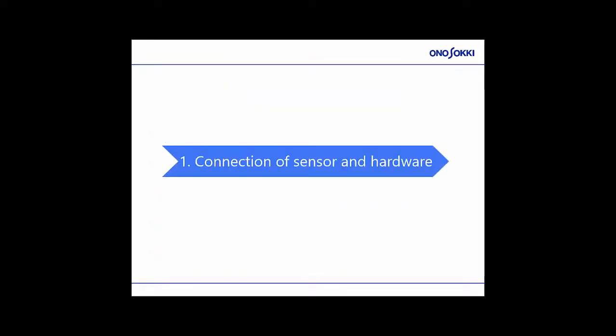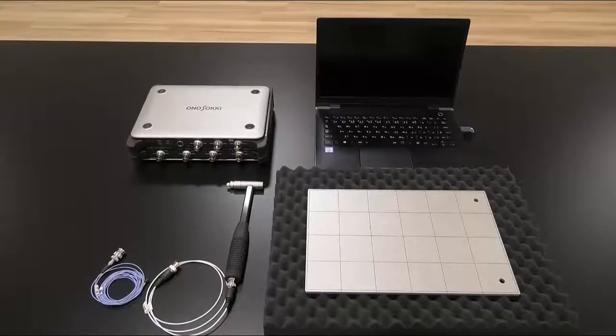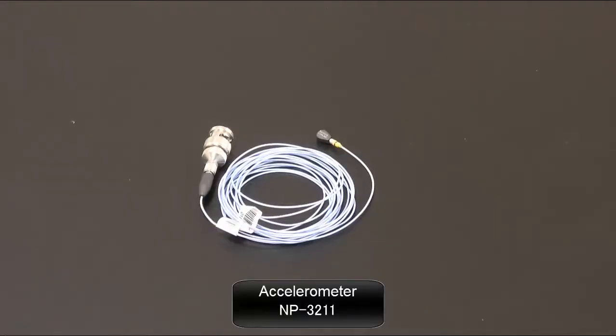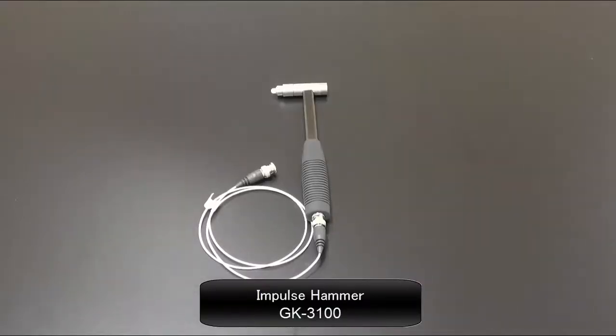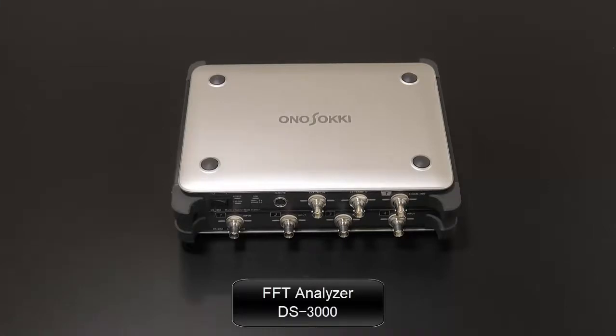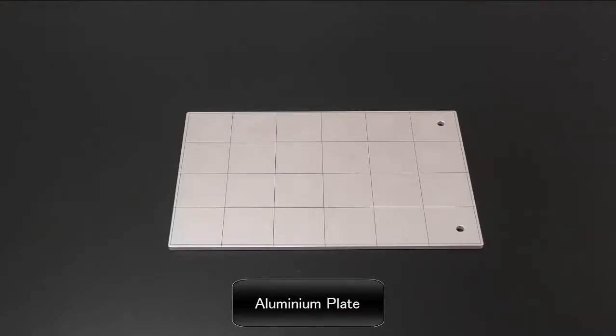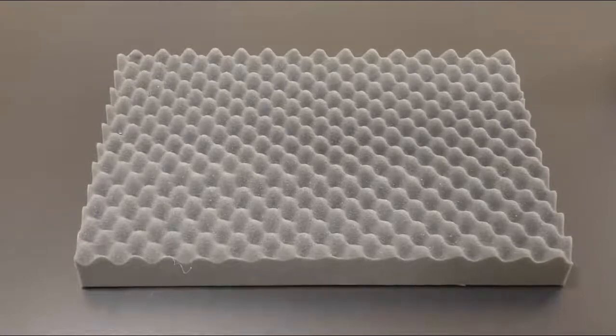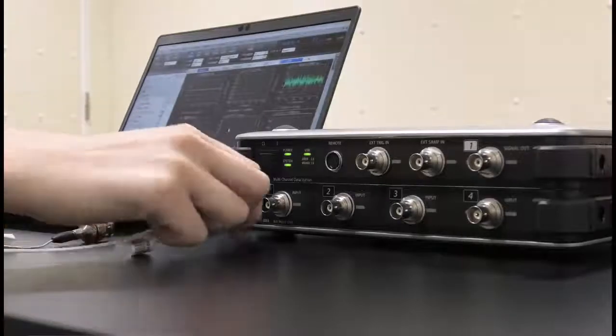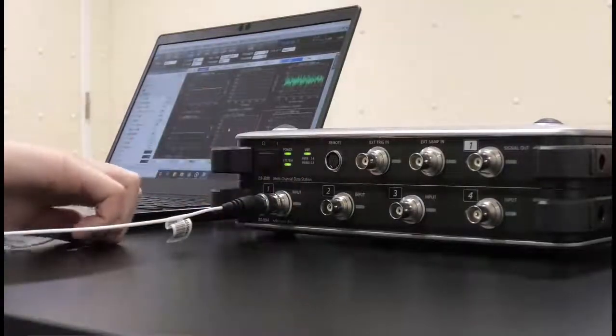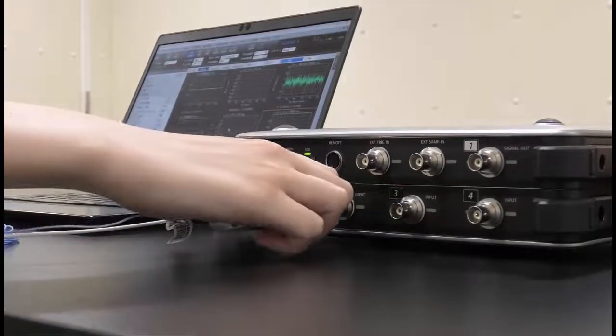One, connection of sensor and hardware. The following items are used for this measurement: accelerometer NP3211, impulse hammer GK3100, FFT analyzer DS-3000, personal computer, aluminum board to be measured, shock absorbing material. Here, connect the impulse hammer to channel 1 and the accelerometer to channel 2.